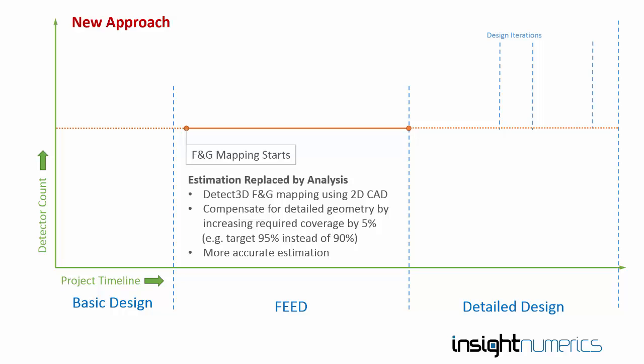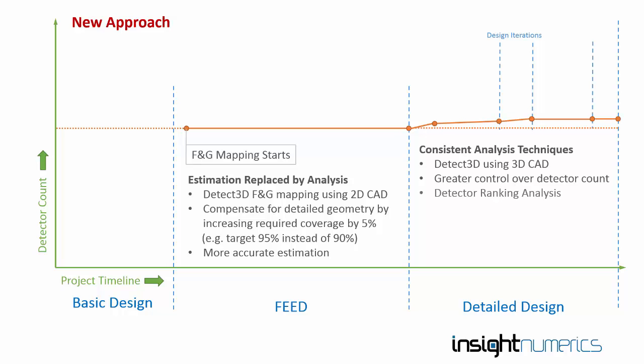Of course, when the 3D CAD is available and you've used Detect 3D through the project, you can simply unload the old geometry which was created from the 2D CAD, load in the new 3D CAD design into the model, and keep all the detectors and zones in place, and resolve any problems with coverage using the various optimisation techniques available in Detect 3D. The important point here is that there is a consistency in the analysis techniques used for detector positioning throughout the project, so any increase in detector count in the detailed design phase is much less dramatic and much easier to handle. Techniques such as using the detector ranking tool in Detect 3D and the upcoming optimisation capability help to minimise any increases further.